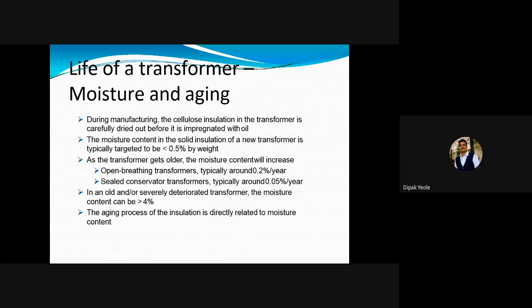Yes, the moisture content, if there is availability of moisture content for that particular oil, then for the solid insulation of a new transformer it is typically targeted to be less than 0.5% by weight. As the transformer gets older, the moisture content will increase.